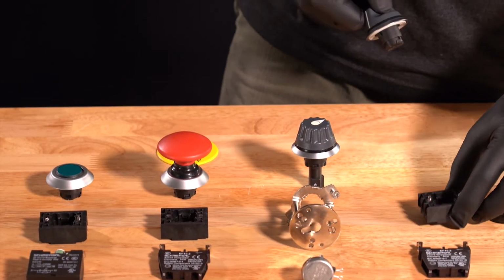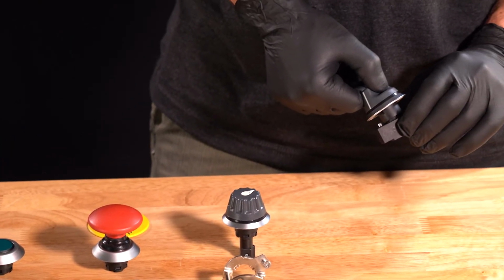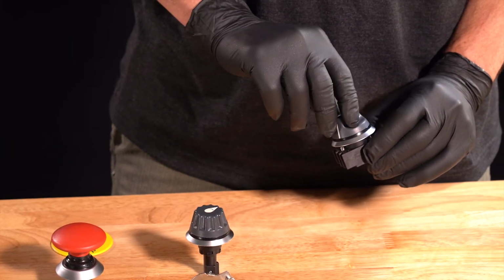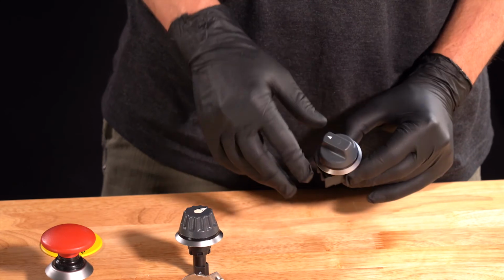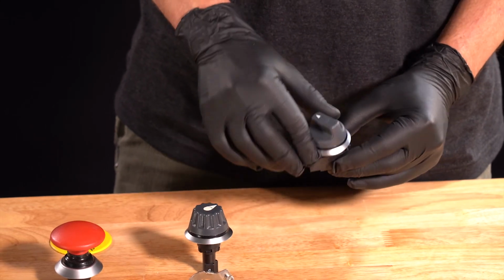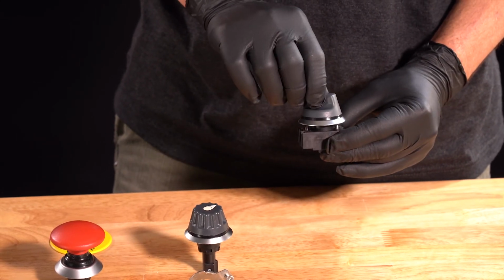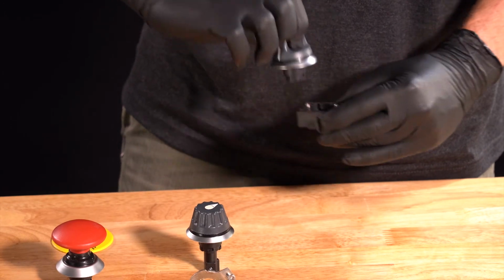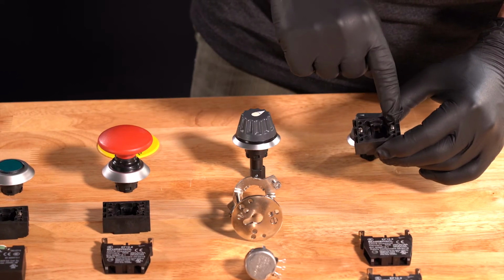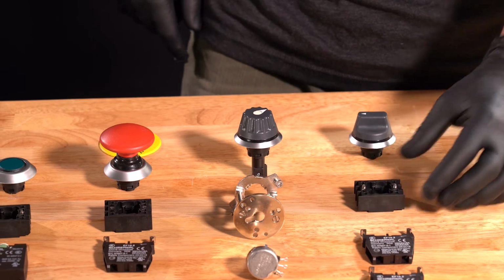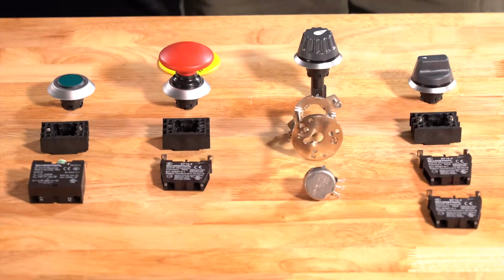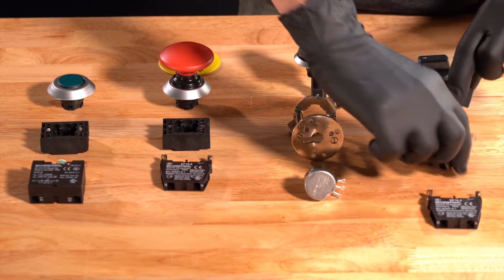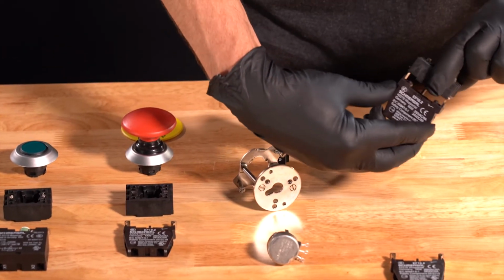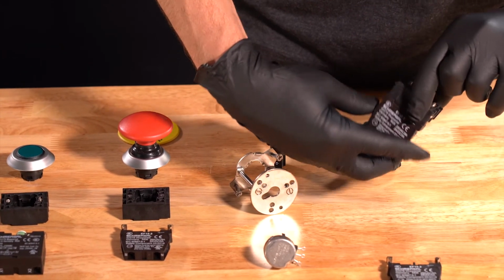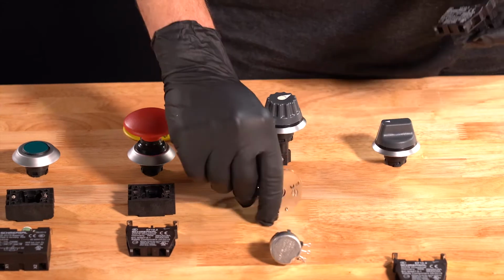Installation of the on-off reverse switch into its mounting block is very simple. The only thing you need to take note of here is orientation when you're installing it on the machine. Plug the switch into the contact block and rotate it a 1/4 turn, and then you can simply use the 2 mounting screws to secure it to the electrical panel. The contact blocks simply snap back onto the mounting base. Take note of orientation before disassembly so you can get it right when you reinstall.